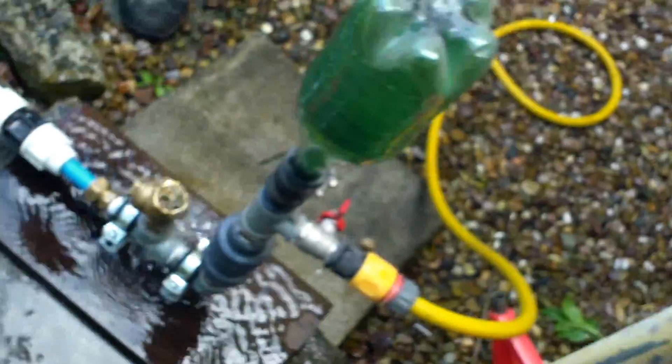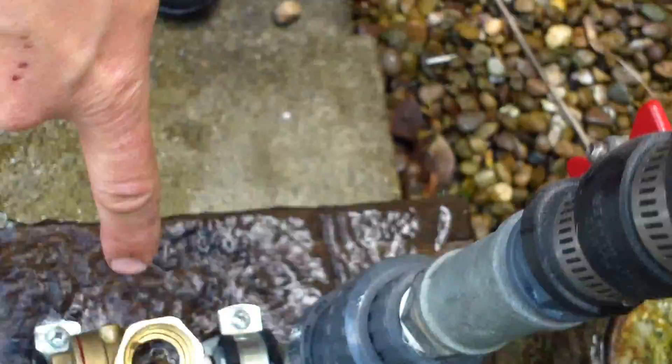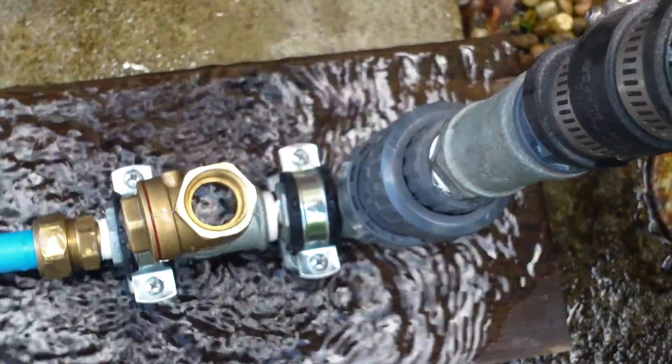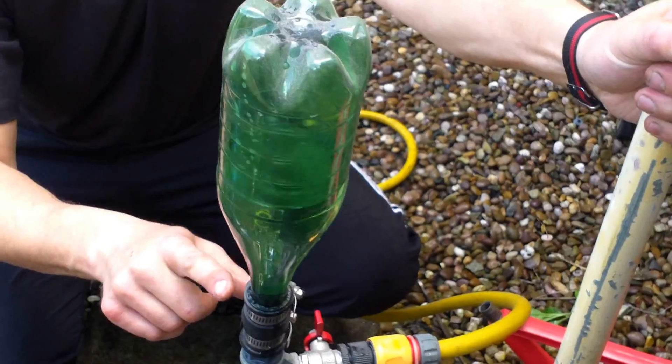Here we are — look at this now. Here's the pump opening and shutting. Swing check valve opening and shutting. Can you get over and look at that? Now this is really tight now. You can see some little minute air bubbles coming up here. There are some little air bubbles — it only needs a few little air bubbles. That stops us getting waterlogged. The pressure is building up here — it's quite tight now.